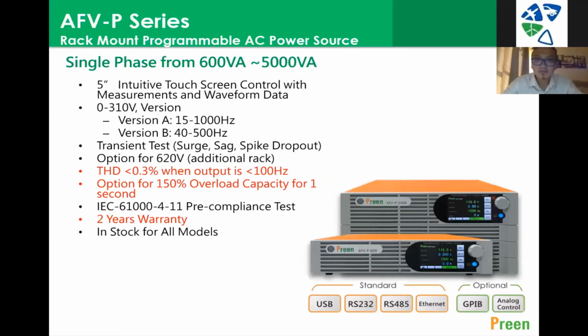If you are talking about the single phase one, usually if your testing unit is small, like a small motor or small home appliance, around below 1 kVA to 3 kVA, the AFV-P is one of the products widely used in home appliance applications, especially single phase, because it supports a wide frequency range from 40 to 500 hertz.